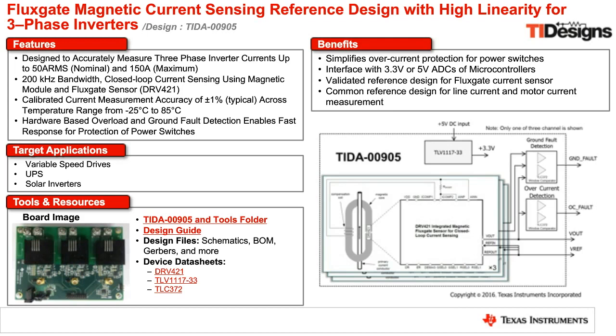This design also shows how to add in overcurrent detection and ground fault detection, using comparators appropriately, the appropriate analog power for these kinds of sensors, as well as some of the amplification stages required on the output. So even if you're not directly interested in designing your own coils, you have the option to review this design, see what kind of accuracies are available, and understand what additional circuitry is required around these sensors.